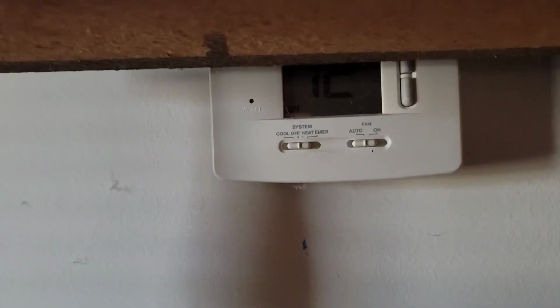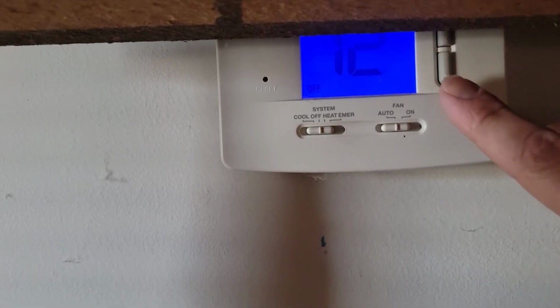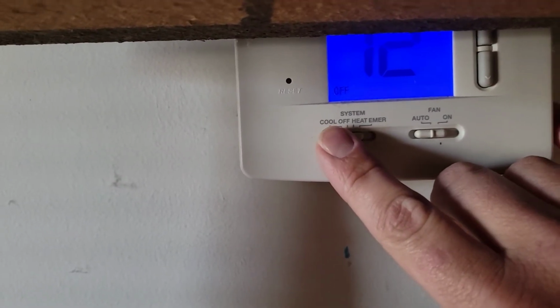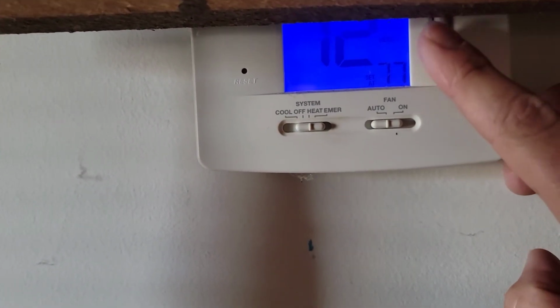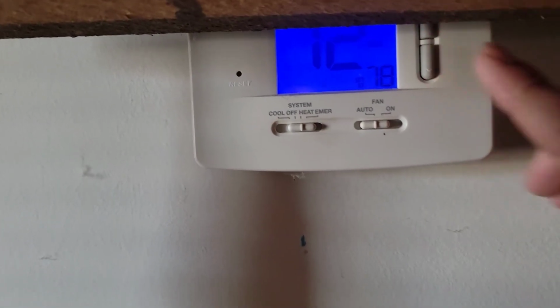So we got a heat pump, it's freezing up, and we're gonna figure out what's wrong with it. So what do we wanna do? We wanna check the heat pump in the heat mode. And first we need to know what the thermostat's set for. So let's check the thermostat. Thermostat's a little bit hard to get to here. It's in the off position. Let's turn it to heat, 72 in here. I'm gonna turn it to 78.